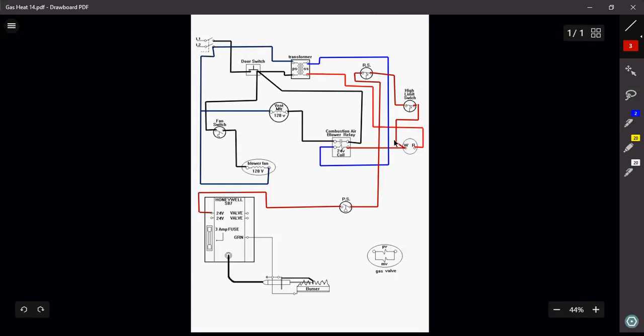But I'm also going to be sending a 24-volt signal out to my safeties. My safeties all have to close. The only way my pressure switch is going to close is if that vent motor is spinning and I have a clear path, and my heat exchanger is in good condition and it's not cracked. Remember, the pressure switch is sensing that pressure difference being created from that vent motor, inducer motor. That guy right there, that's very, very important to understand what that pressure switch is doing.